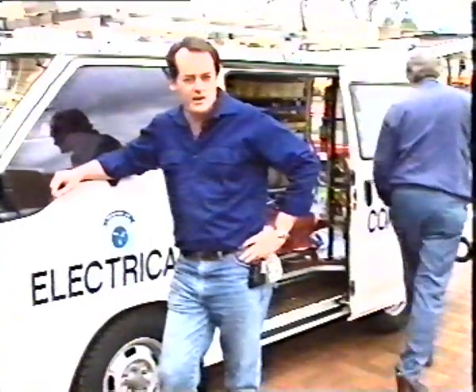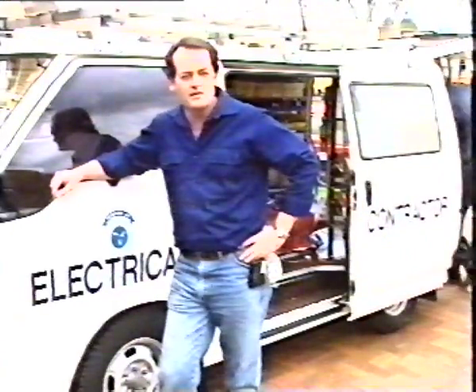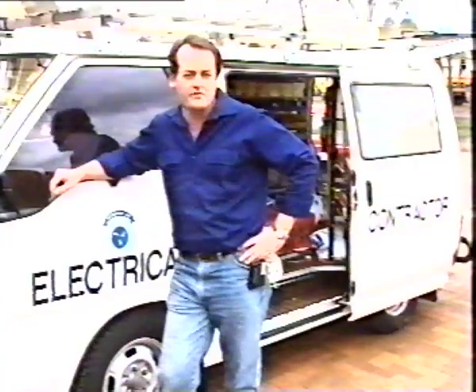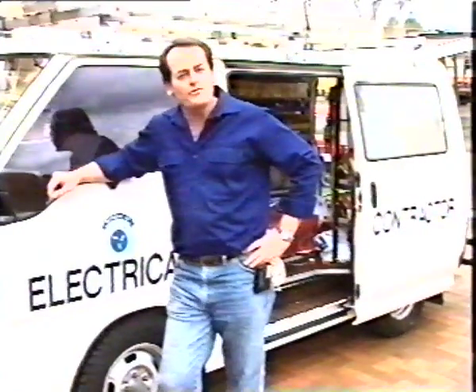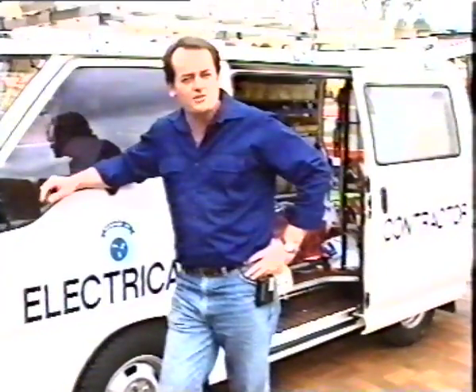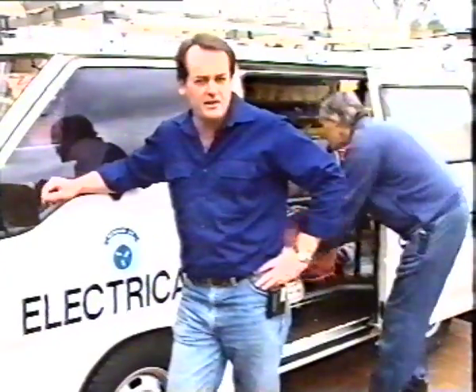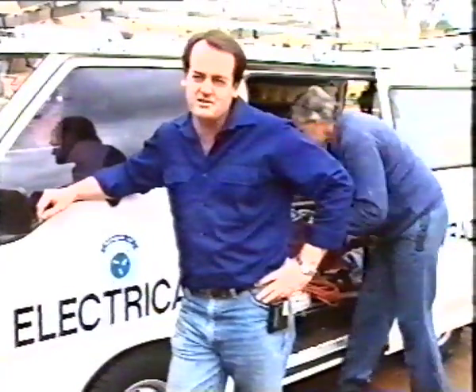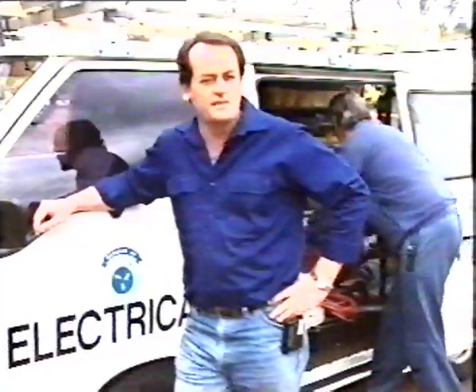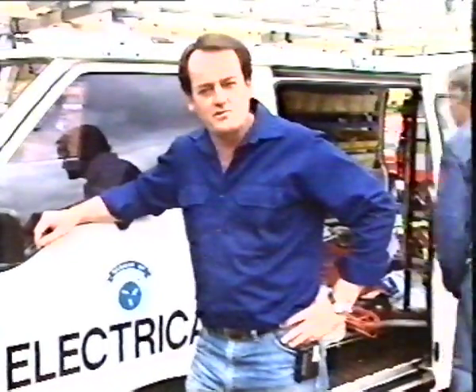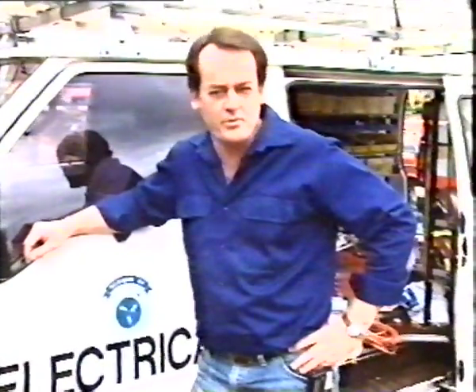This percentage will drop to 90 by the end of the first year and then progressively reduce to 50% over 5 years. The electrical contractor will be responsible for the actual testing, while the electrical inspector may inspect the installation but not necessarily test it. To date, the principles of electrical circuit testing have not been taught as a separate component of the electrical trades course, but the fundamentals of electricity still apply to testing. There are precise techniques which the installing electrician will need to use competently.